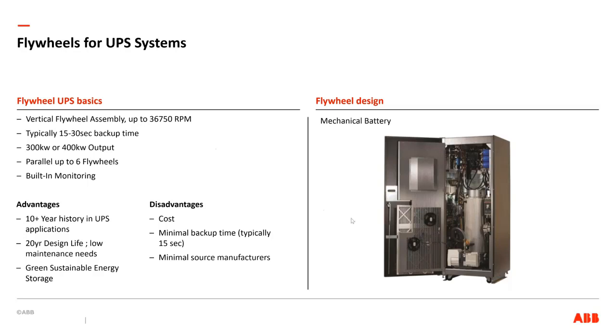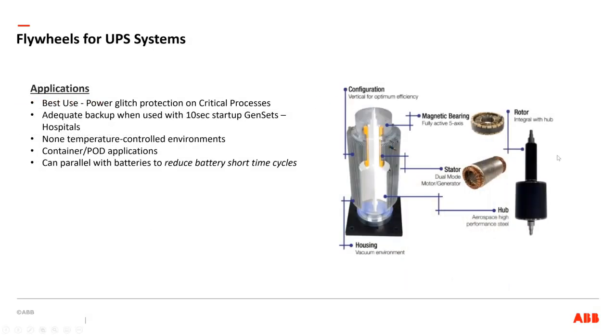There are benefits. There are customers using flywheels, actually very, very few in the IT world. It happens, but we see them a lot more in the healthcare sector. They are good rugged devices, and there are benefits with a flywheel. They're typically a 20-year design life, and they live for 20 years. That's a major difference compared to the batteries, where the actual life typically is half of the design life or maybe a little bit more. And there's no toxic material, other than electronics, but lead is toxic. We have a very good recycling system for lead, but it is toxic. The flywheel is a nice green solution when it comes to that.